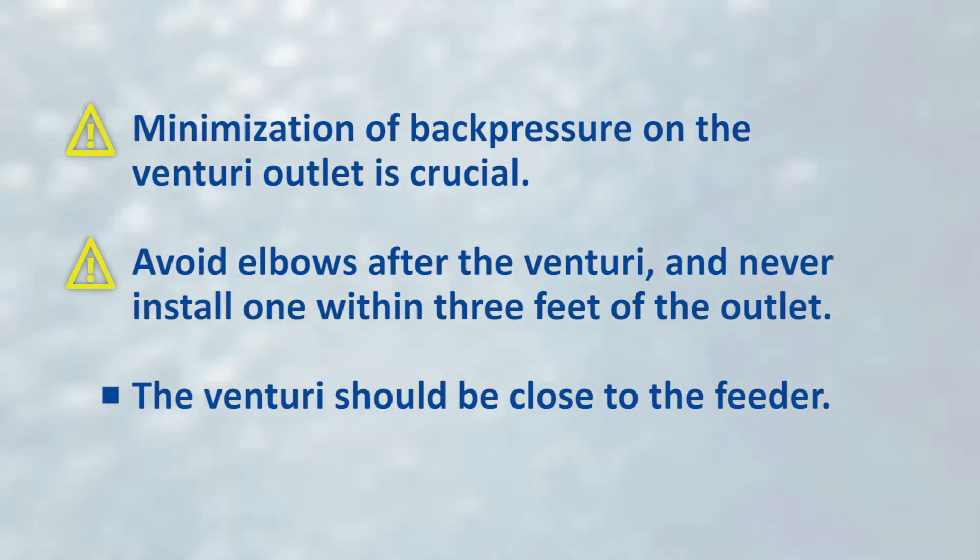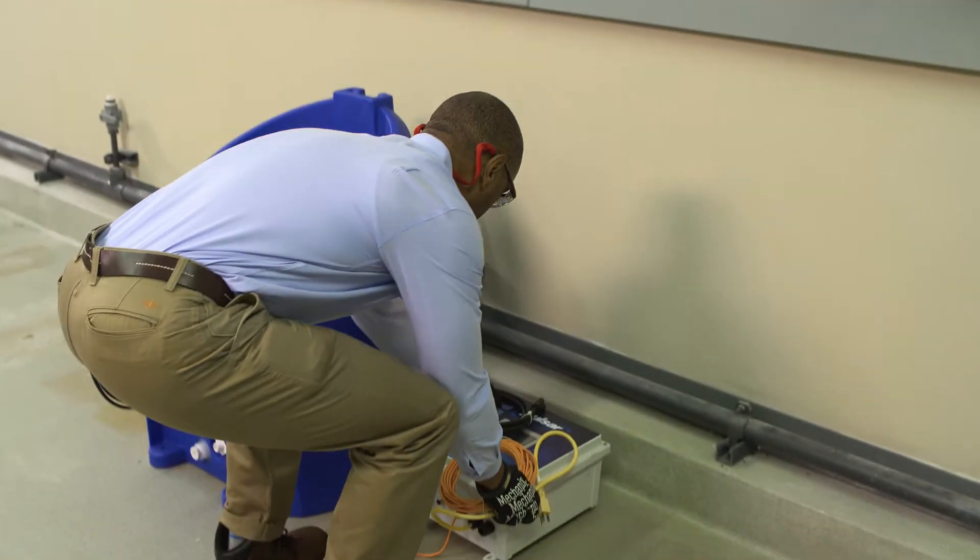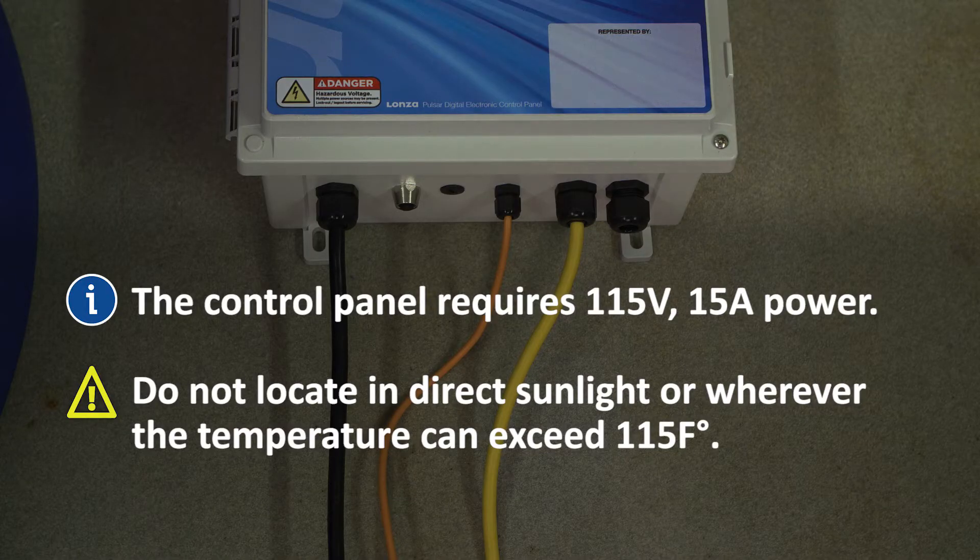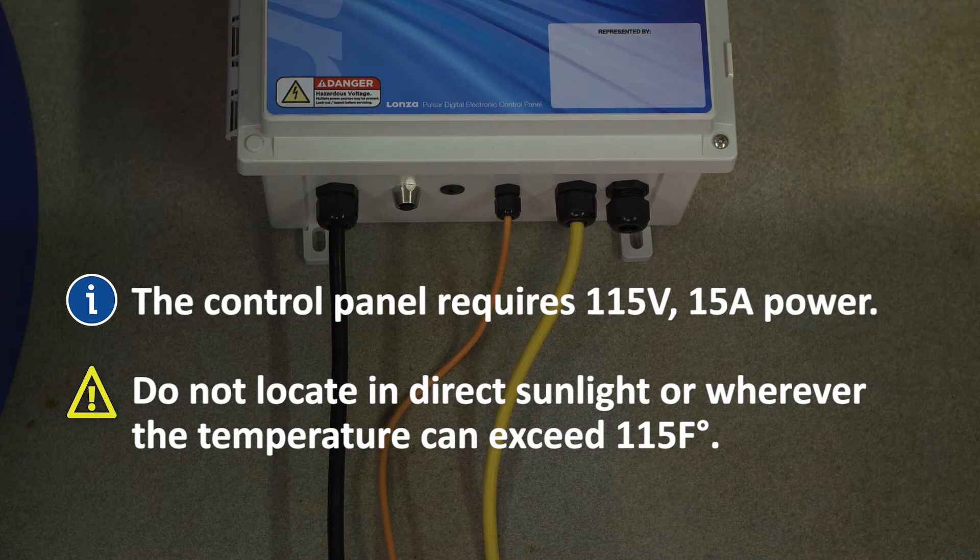The venturi should be close to the feeder to reduce distance and elevation between the venturi suction and feeder discharge. Position the control panel close to the feeder. The control panel requires 115 volts, 15 amp power, which also powers the booster pump.